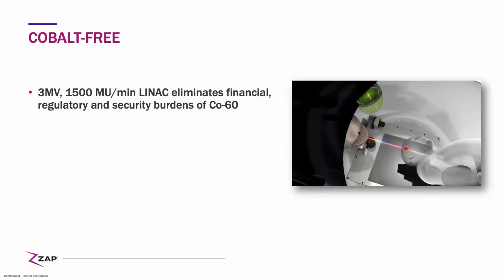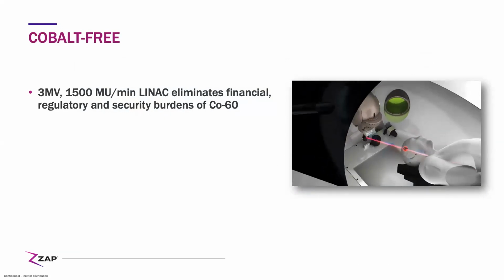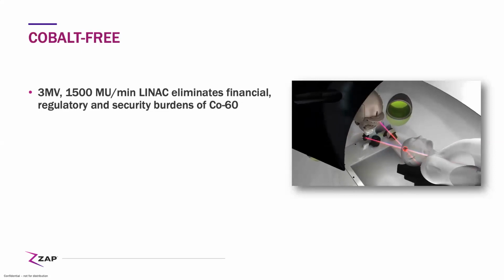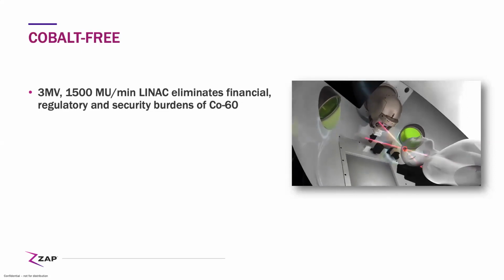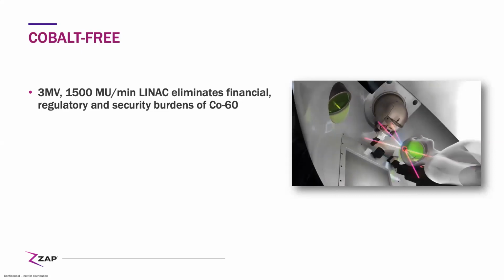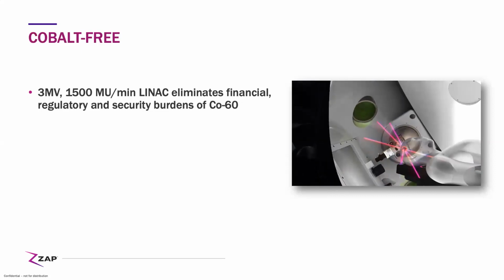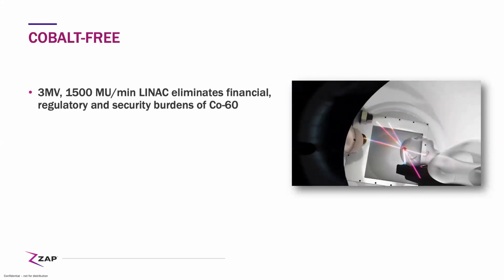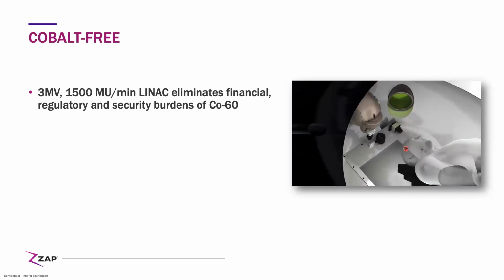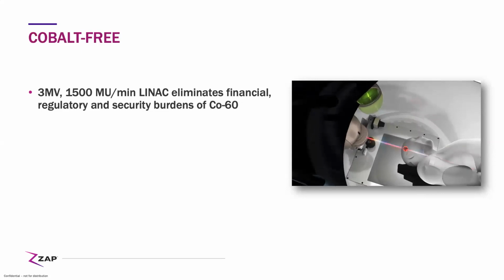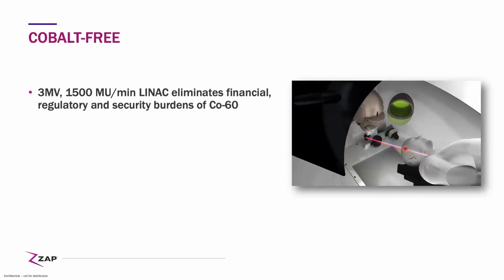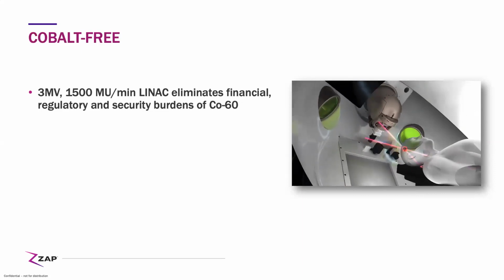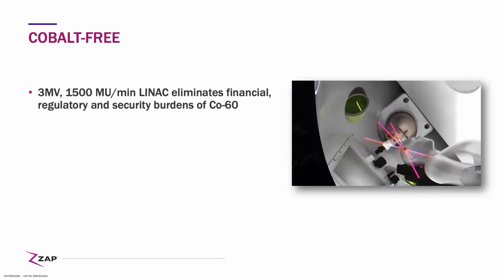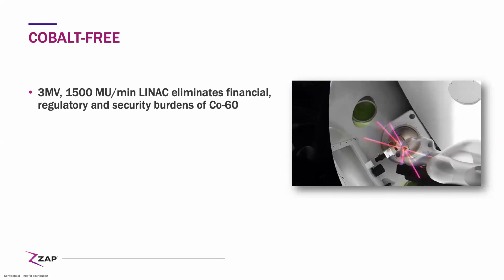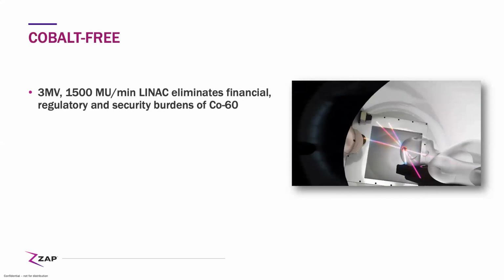What's also striking about the ZAP-X is it's cobalt-free, getting rid of all the regulatory apparatus that overlies traditional cobalt. You can see that there's a 3 MV Linac, whose average energy approximates that of the cobalt photons, delivers a very high output of 1,500 rad per minute, 1,500 monitor units per minute, and just makes for very fast treatments without all of the financial and regulatory and ultimately the security problems associated with cobalt.